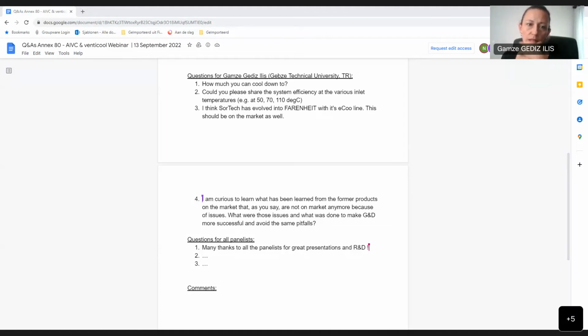The other question is, could you please share the system efficiency? It depends on the system, and again on the temperature of the system, how much wastage you have, the inlet temperature of the chilled water, and also the ambient temperature. The general COP of these systems is around 0.5 to 0.6, but we achieved 0.85, which is the highest value in the market right now.